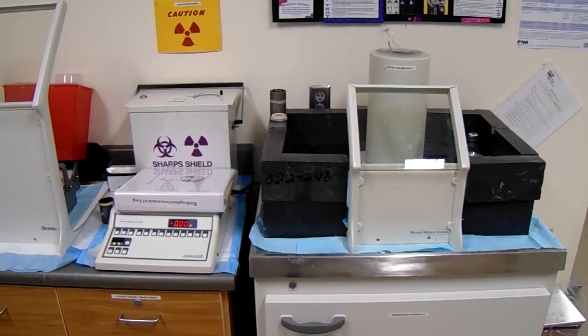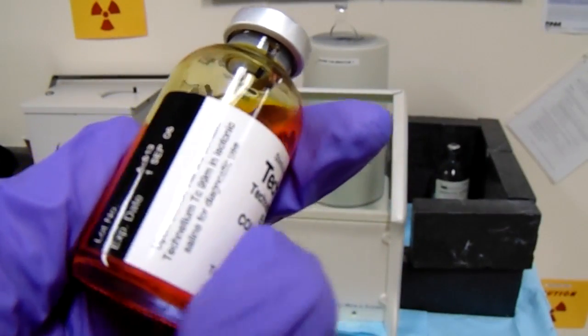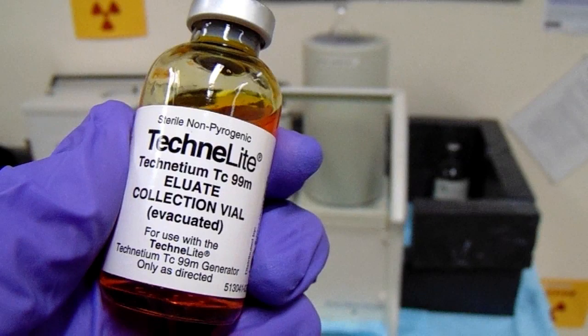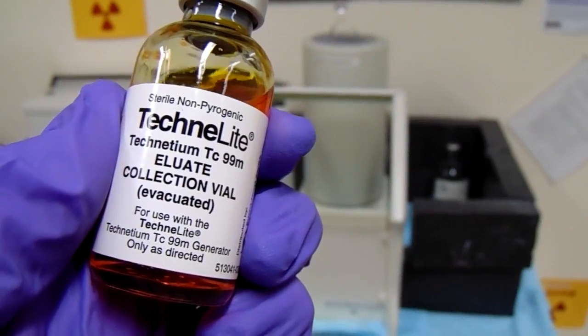Now that we have our elution, we need to test it for alumina and moly breakthrough. In order to do that, we're going to need to use our dose calibrator. The reason we test for molybdenum breakthrough and alumina breakthrough is because aluminum is very toxic to the body, and molybdenum has an extremely high energy keV photon as well as being a beta emitter, so it can cause severe damage to our patients if we inject a dose with too much molybdenum in it.